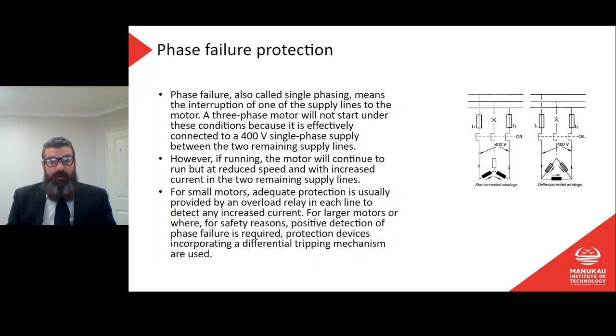Phase failure, also called single phasing, means the interruption of one of the supply lines to the motor. So, as I said before, single phasing means we've lost one phase. We still have two phases, but we call it single phasing because we've lost one phase. A three-phase motor will not start under these conditions because it effectively connects a 400 volt single phase supply between the two remaining supply lines. That may or may not make sense to you. Take that for what it is at the moment. We need all three phases for a motor to start.